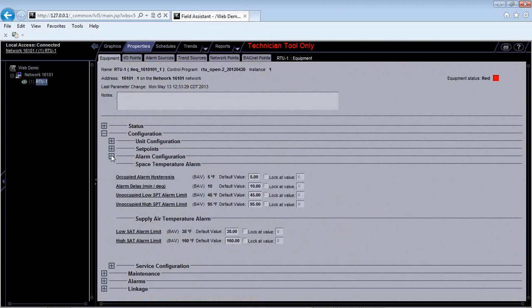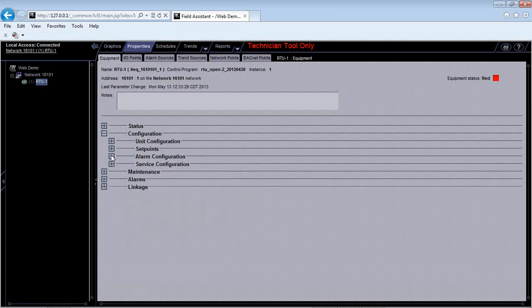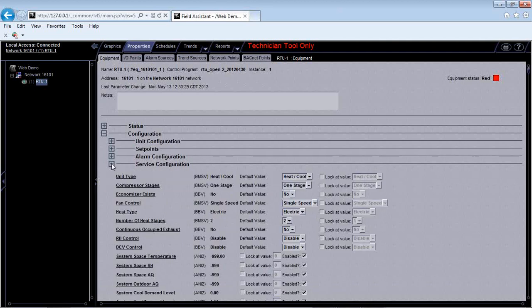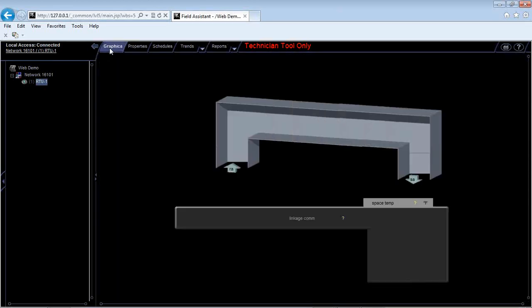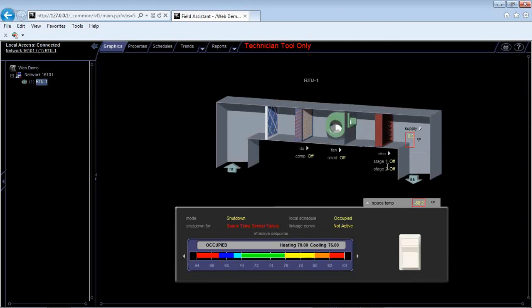Alarm configuration is not that helpful right now. It's something that you kind of just want to default. We'll go into the alarm sources tab to show you a little bit more information on that. But service configuration is the other big one that you want to look at here. So this is where you tell your unit what type of unit you have. If you remember when we looked at the graphic over here, we saw we have 2 stages of electric heat, DX, no economizer. We're just recirculating air.